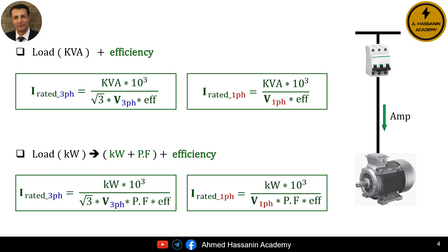We must note that if the load value is given in KW and we want to calculate the rated load current, we also need the power factor in addition to the load value in KW. If we do not have the power factor value, we can assume it to be 0.8. For the case where the load value is in KW and we have the power factor and efficiency of the motor, for a three-phase dynamic load or three-phase motor, the equation for the rated current is the rated power in KW multiplied by 10 cubed, divided by the square root of 3, the three-phase rated voltage in volts, the power factor, and the efficiency of the motor.